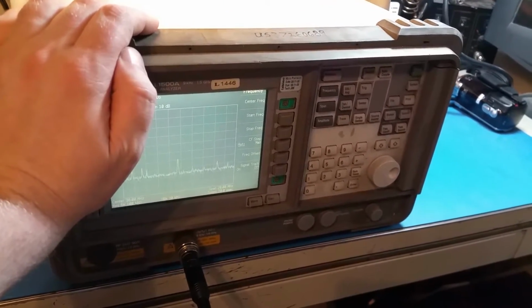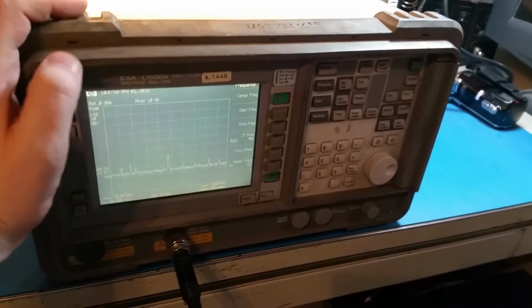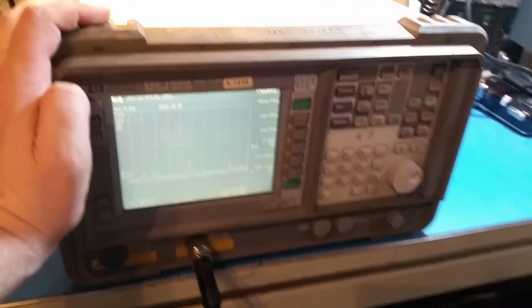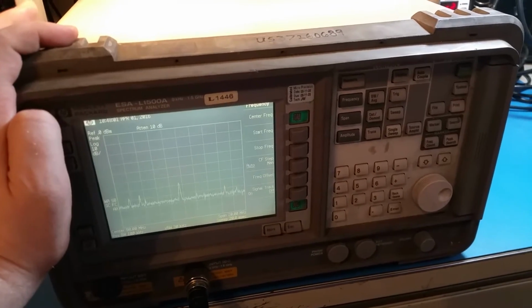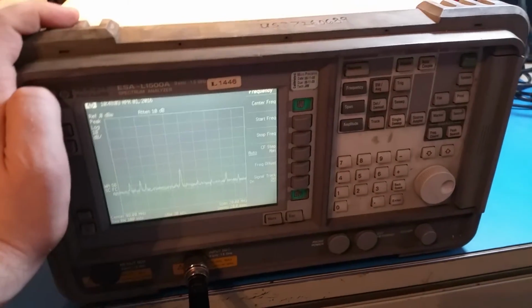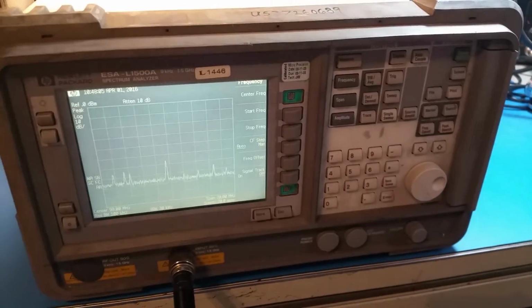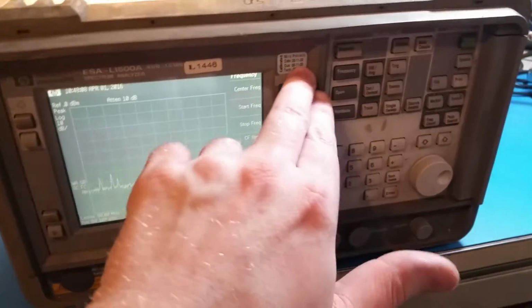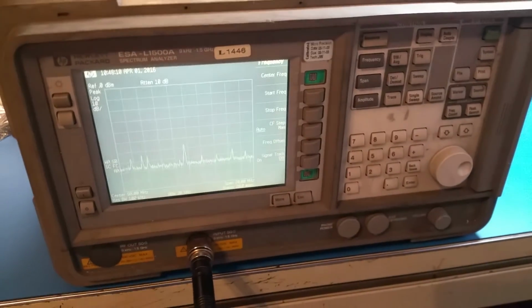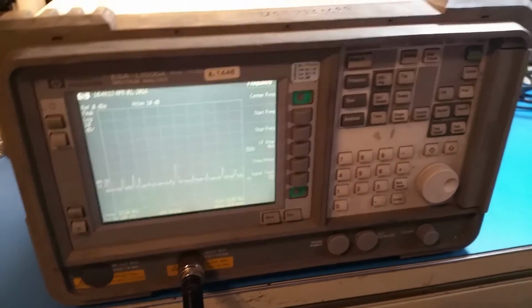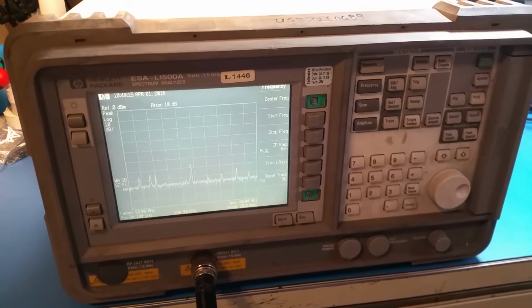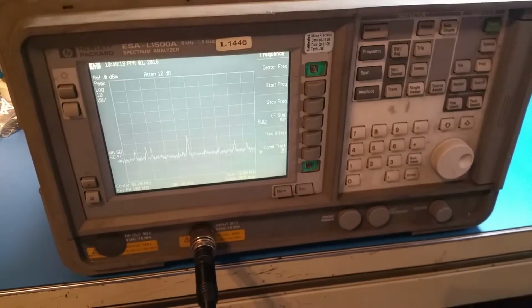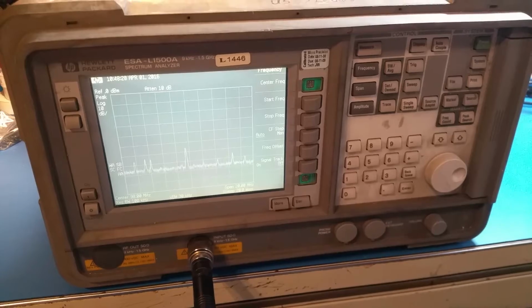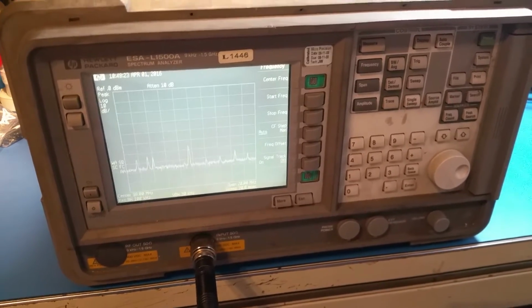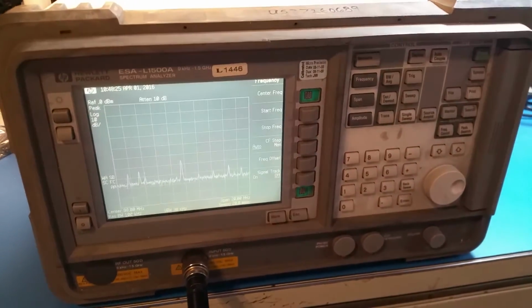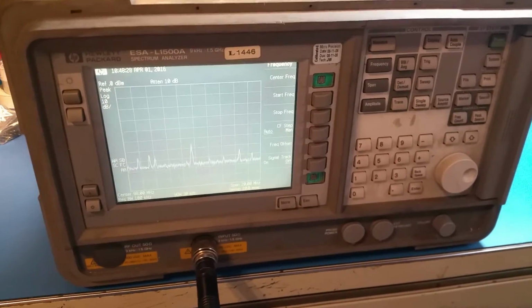it would be a good idea if anybody that watches this picks one of these things up on eBay like I did, to give it a good once over. Unless it's been calibrated and tested and all that kind of stuff. This one hasn't been since 2009, so it's got no recent cal. I don't care about opening it up and breaking somebody's cal seals, because that chirping, the fact that it's now getting less and less the longer it's running, is an ominous sign of capacitors and the power supply.